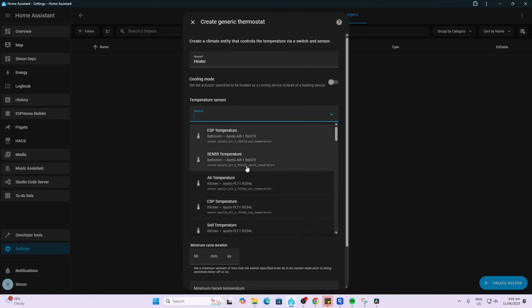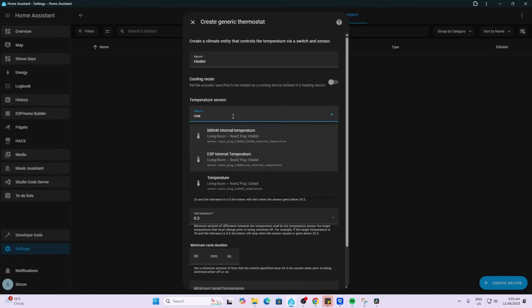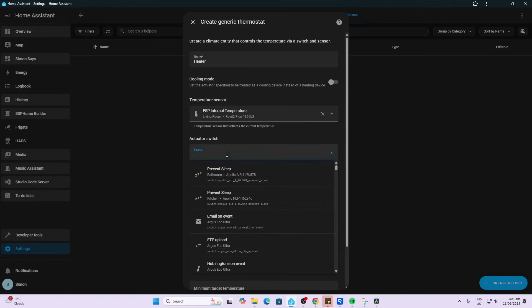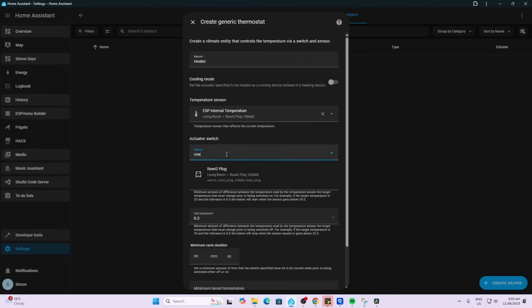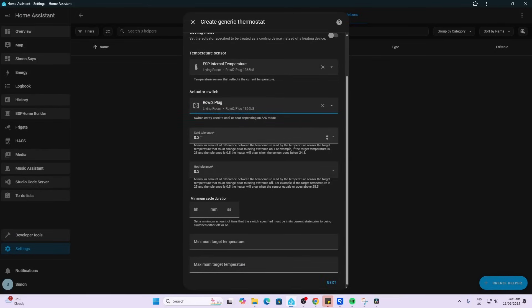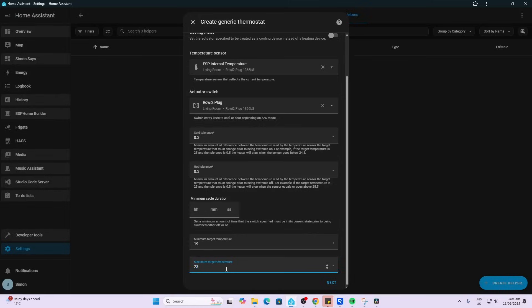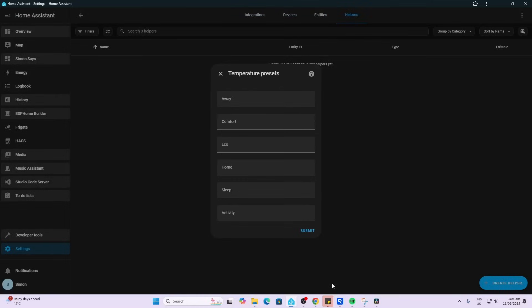We're going to select our temperature sensor. So we want to have the temperature sensor. We want to select our switch. There's the actual switch. Now we can set our tolerance. So this is designed for how far it will allow the temperature to go before it turns on and off. You can adjust that. You can also adjust your minimum cycle duration. And this is our target temperature. So you can select here whatever temperatures you'd like to be able to set on the thermostat. So I'm going to say from 19 degrees through to 23 degrees.